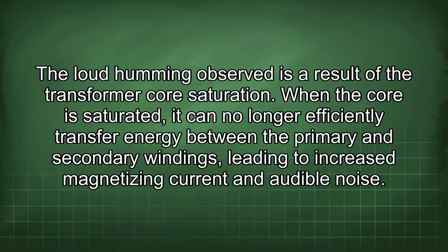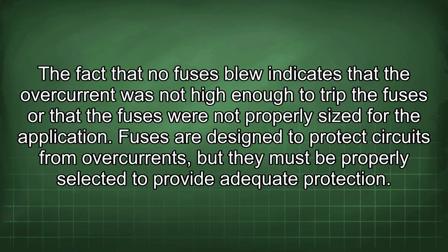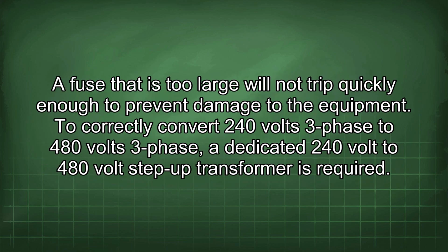The loud humming observed is a result of the transformer core saturation. When the core is saturated, it can no longer efficiently transfer energy between the primary and secondary windings, leading to increased magnetizing current and audible noise. The fact that no fuses blew indicates that the overcurrent was not high enough to trip the fuses or that the fuses were not properly sized for the application. Fuses are designed to protect circuits from overcurrents, but they must be properly selected to provide adequate protection. A fuse that is too large will not trip quickly enough to prevent damage to the equipment.